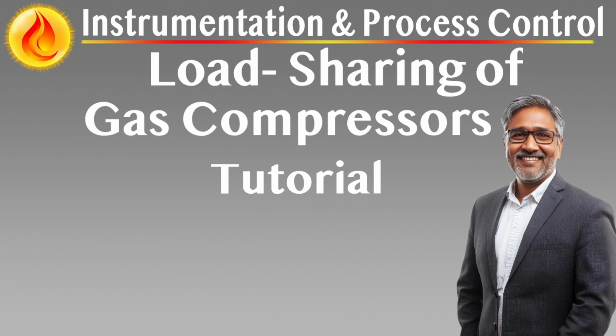Load balancing. Each compressor's anti-surge controller calculates its deviation from surge, DV. The load-sharing controller selects the worst-case DV from companion units and aligns its own output. Averages are computed across all compressors to establish a system-wide load balancing set point. Flow rates are then modulated to ensure each compressor runs equidistant from its surge limit.